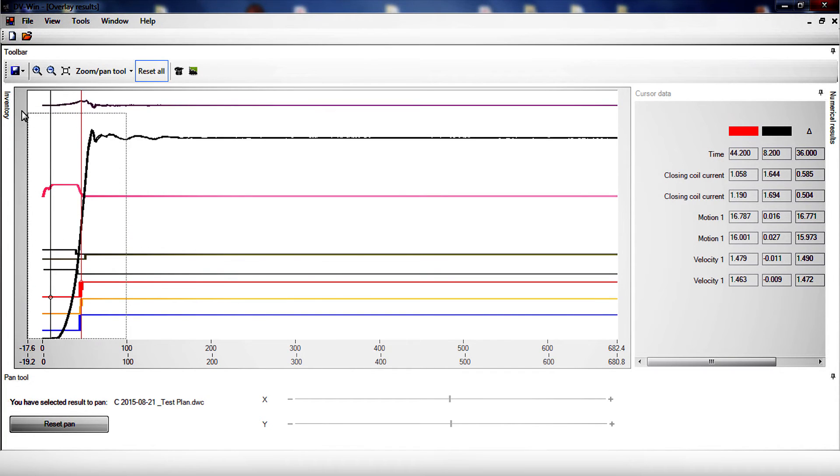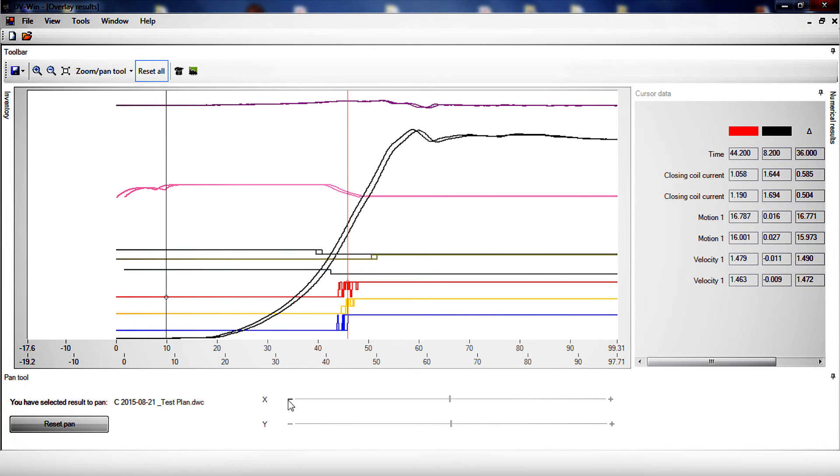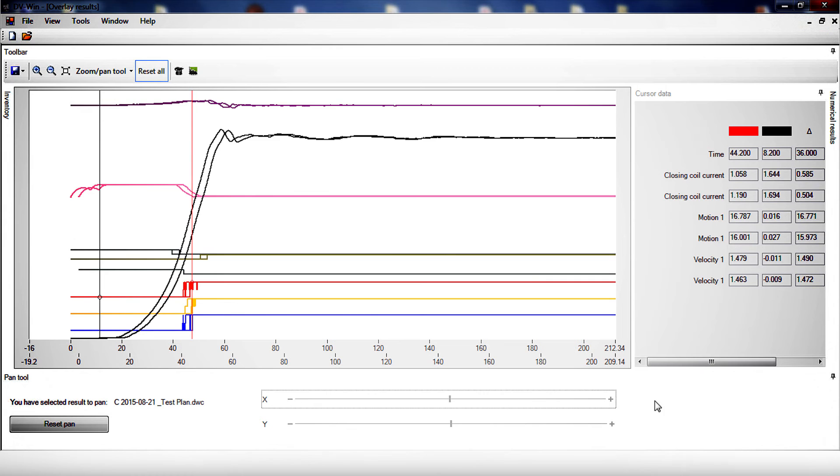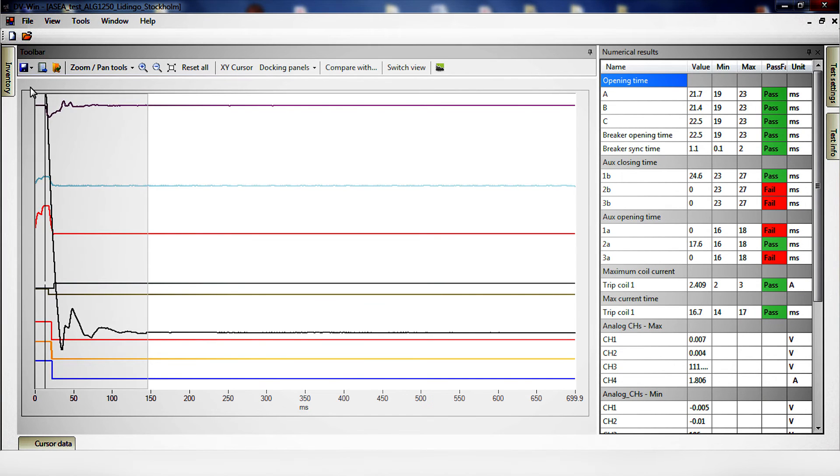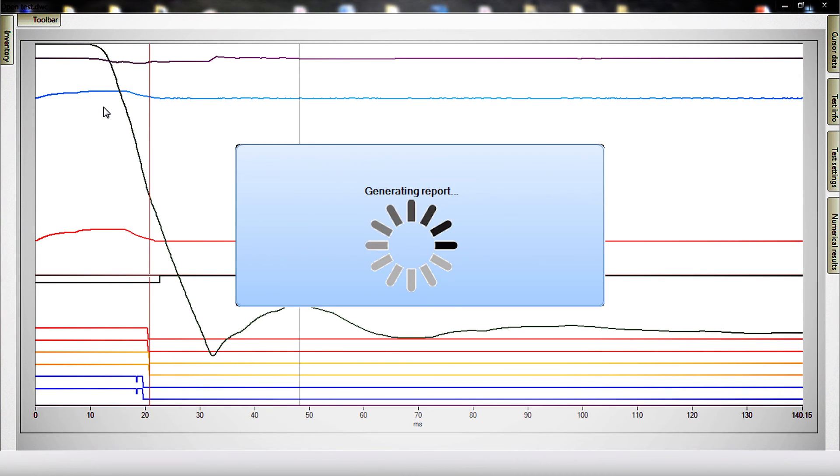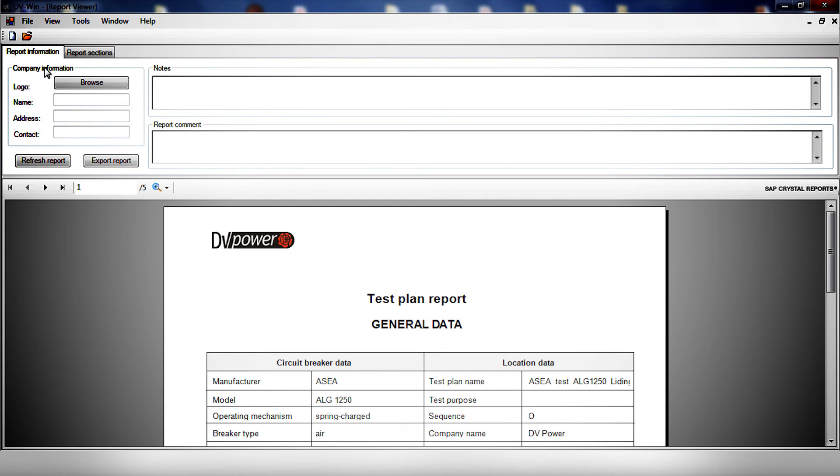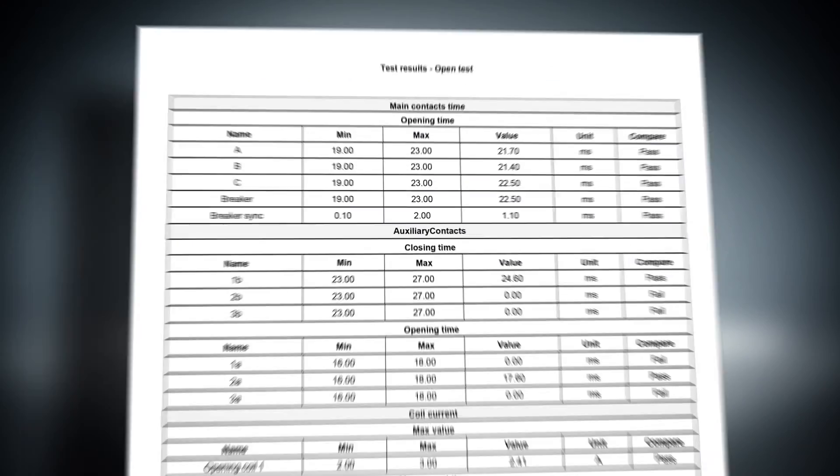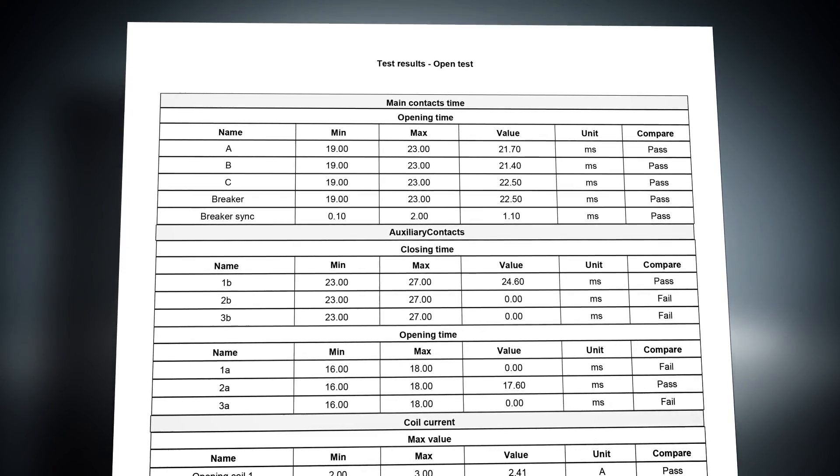An essential part of circuit breaker condition assessment is the ability to compare the latest test results with results obtained in previous tests. Measured values are compared with limits specified by the manufacturer. The obtained fingerprint can be used at a later stage as a reference for subsequent measurements. In order to provide accurate comparison, tests need to be performed using identical test parameters. Any deviation and change in test results may indicate circuit breaker condition deterioration. This ability is supported by DV-WIN test plans and graph overlay feature. The final stage of a circuit breaker maintenance process is the DV-WIN providing analytical tools and customized report creation.